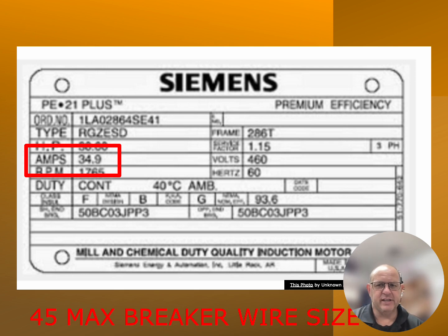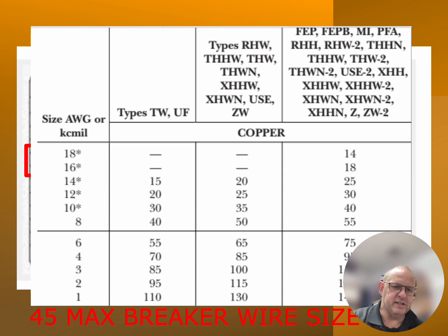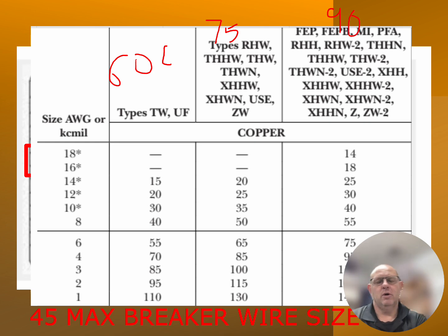Now, what I will do is I will go to the NEC, the National Electric Code, and I will see what type of wire I can install for this 45 amp breaker that we're going to install for this particular motor that's out there. So using the NEC, I'm going to go down through. I don't know what type of wire I'm going to use, and I do not know the termination fittings that are on that particular wire. Some of these are 60 degrees Celsius. This one's 75 degrees Celsius. And this one is 90 degrees Celsius. If I do not know the termination temperature at which the unit is going to be running, then I always have to use the lower or the cooler number for those wires.